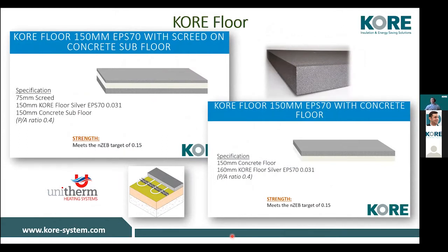So a couple of floor calculations for you first. Typical scenarios. For both of these, we picked a perimeter area ratio of 0.4. So your perimeter versus the area of your floors. So standard build, we have a 75 mil screed, we have an insulation, and we have a 150 mil subfloor. So if we're using underfloor heating here, our U-value target is 0.15 to comply with our building regulations. To get there, all we need is 150 mil of our silver EPS.